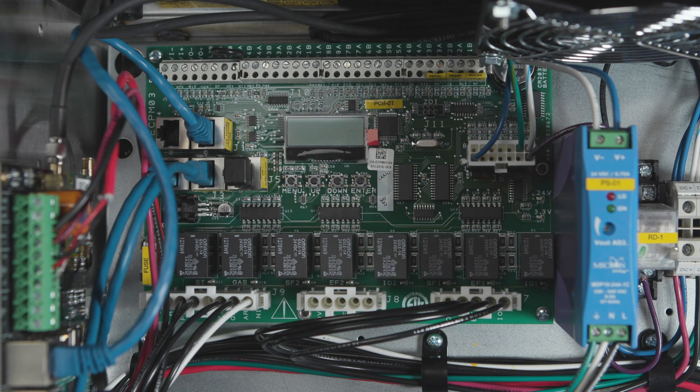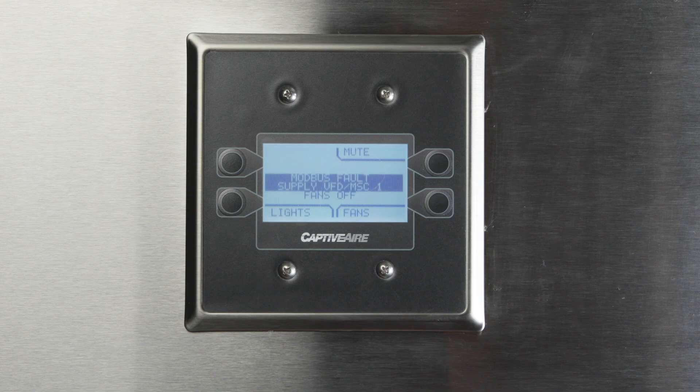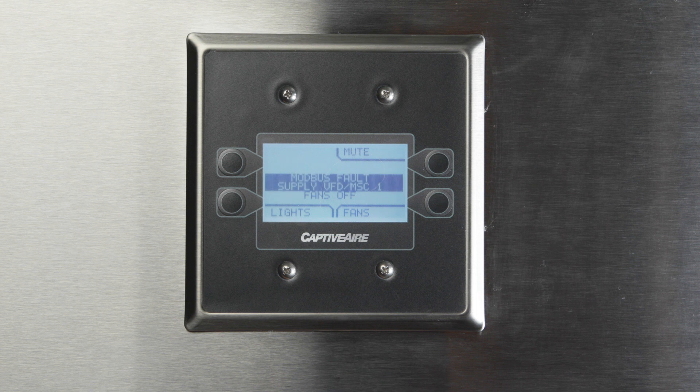First, if you power up the circuit board, but do not power up the VFDs, the HMI will show you a Modbus communication fault. That simply means that the circuit board can't see the VFD because it's not powered up and able to communicate.